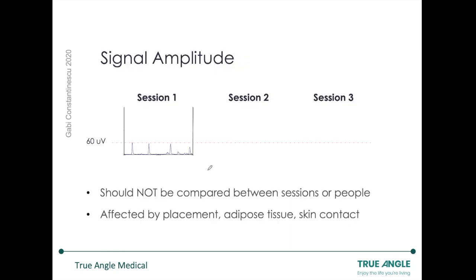Let's start off with one thing that I learned much too late into using SEMG in clinic, and that is that signal amplitude should not be compared between sessions or people. Many years ago, I remember sitting down with patients, I had them hooked up to the KayPENTAX, and I diligently marked down their amplitude trial after trial. After their treatment, I would make a report graphing their amplitude changes. So if I had a patient come in for session number one, I would sit down and go, okay, your swallowing muscles are contracting at about 60 microvolts — that's great. And the next day they'd come in and I'd go, that's odd, you're not doing so well today, you must be having an off day.